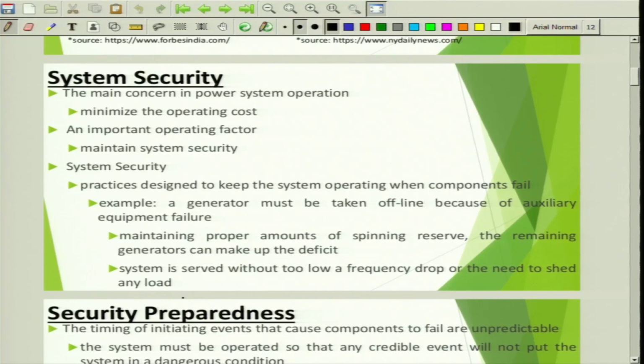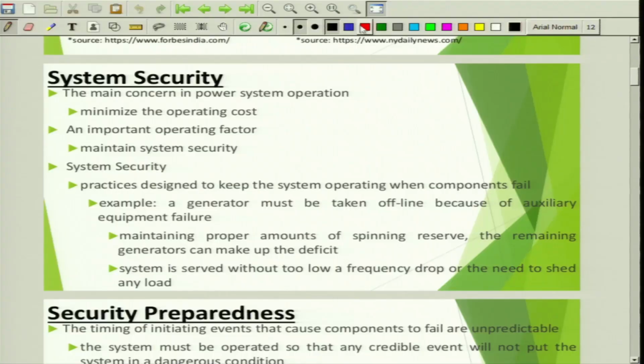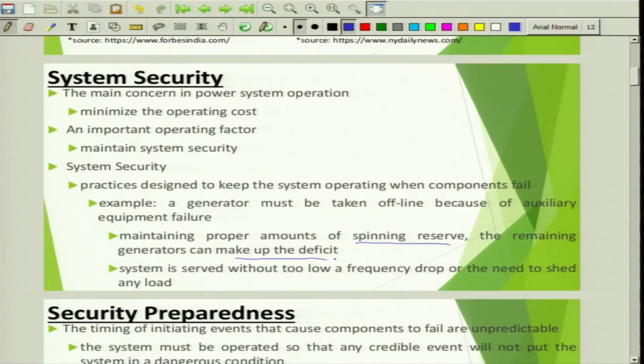If there is an issue with one specific generator, a fault within a generator, then that generator has to be taken out. But we ensure that with proper spinning reserve. I discussed spinning reserve in the previous class, right. With spinning reserve, the remaining generators can make up the deficit. That is what we consider as n-1 contingency: with one generator out, the system is still supposed to cater to the requirement of the load. The system is served without too low a frequency drop or the need to shed any load.